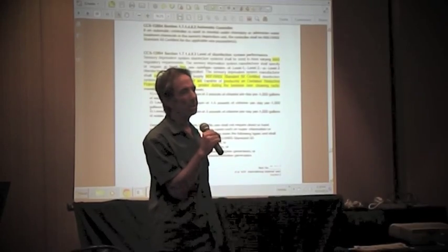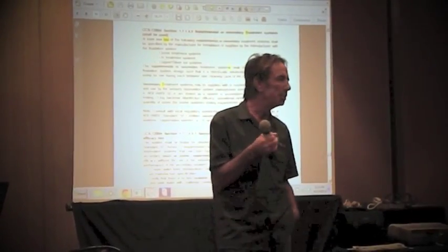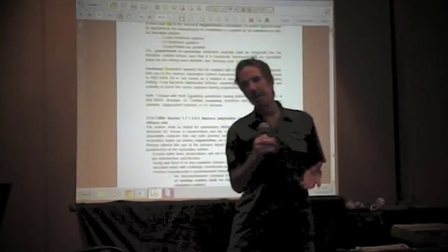So it kind of worked for us in both ways. The solution now at NSF, while they were trying to determine how long to run the chemical feeder there, to insert the residual, they found that they were unable to determine the parts per million accurately in the solution. So now we have the situation where people are dumping chemicals into this solution that somebody's in, with no ability to monitor what they're doing. There's no method of monitoring the parts per million in this solution. Yet the regulatory systems now are still reliant on this style of verification in recreational water facilities.